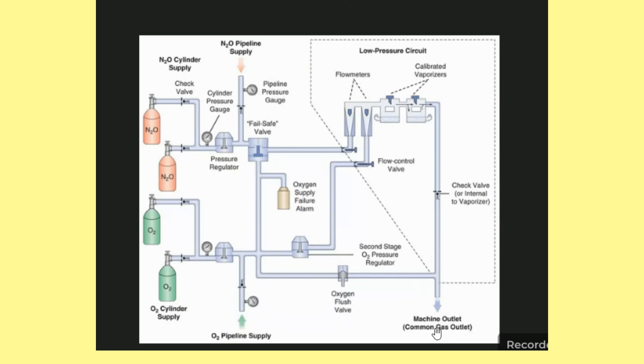The patient circuit connects to the anesthesia workstation. The anesthesia workstation comes with ventilator support. Most of the systems will have a secondary stage pressure gauge for the central oxygen supply to monitor the secondary pressure.